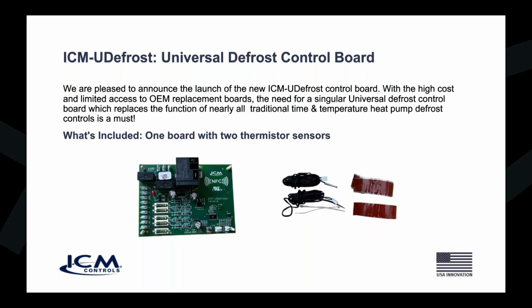We needed a singular universal control, which replaces the function of nearly all traditional time and temperature heat pump defrost controls, and that's why we developed this product, the ICM-UDefrost Universal Defrost Control Board. It comes with two sensors, one onboard sensor and one auxiliary outdoor air ambient temperature sensor, which is used for specific applications to set up the control to lock out the heat pump when it can no longer have good thermal transfer. If the temperature is sub-zero outside, there's no point in running your heat pump. You're going to have to run off your auxiliary heat source, so we can lock the heat pump out. This board has the capability of locking out the heat pump when it's not going to be efficient.